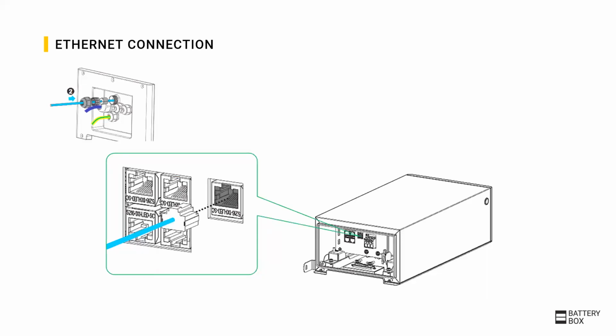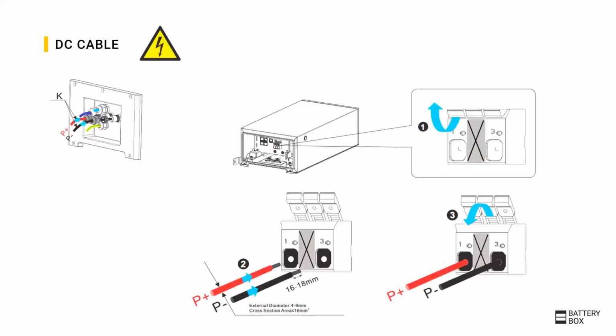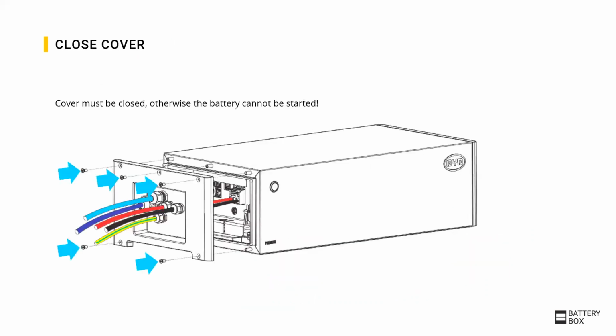Next is the optional Ethernet cable to establish an internet connection. It is optional, but we highly recommend it to allow for remote updates and remote service. The DC cable connection is shown here. You can use DC cables with up to 16 square millimeters. After connecting all cables, close the cover. The battery cannot be started if the cover is not closed correctly.